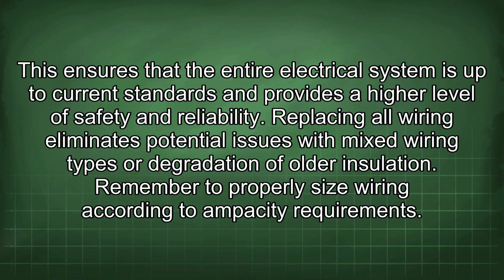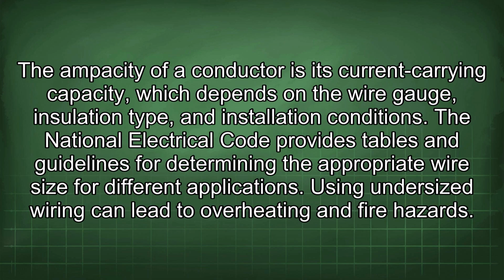Remember to properly size wiring according to ampacity requirements. The ampacity of a conductor is its current carrying capacity, which depends on the wire gauge, insulation type, and installation conditions. The National Electrical Code provides tables and guidelines for determining the appropriate wire size for different applications. Using undersized wiring can lead to overheating and fire hazards.